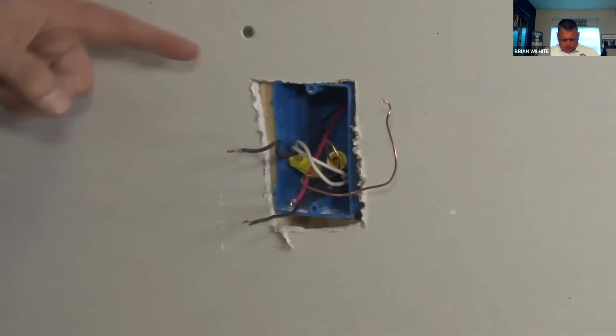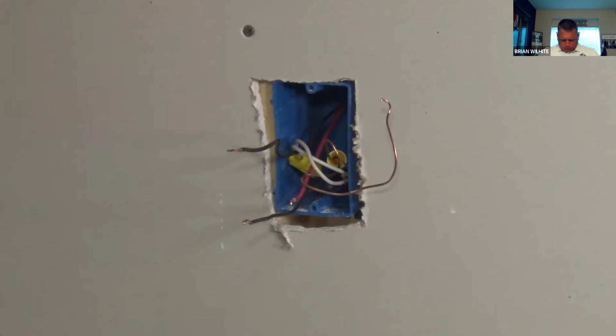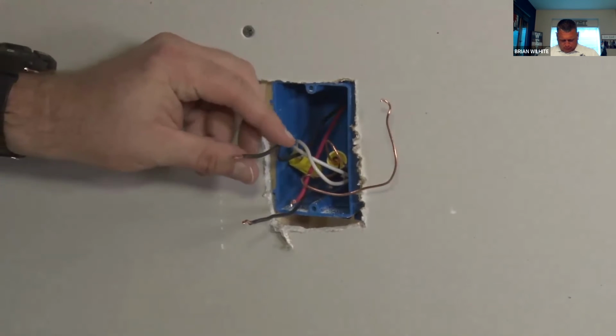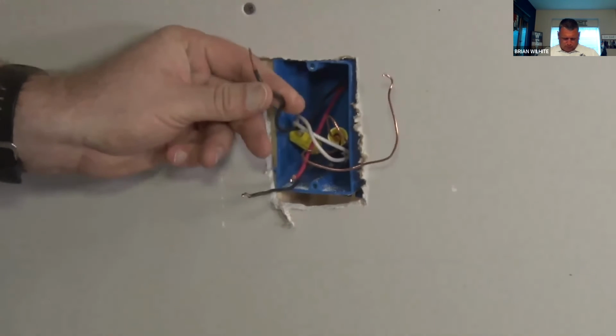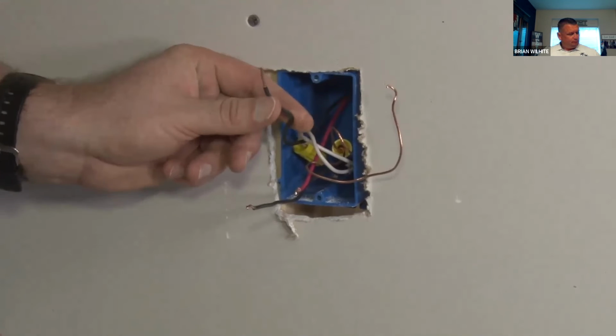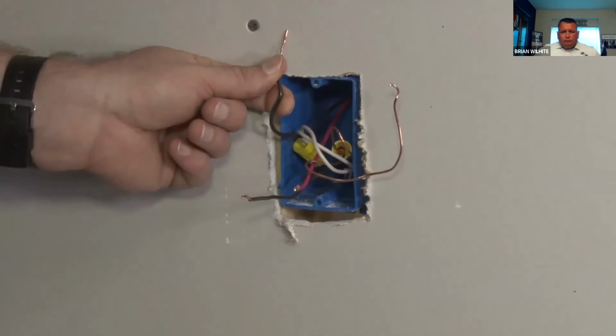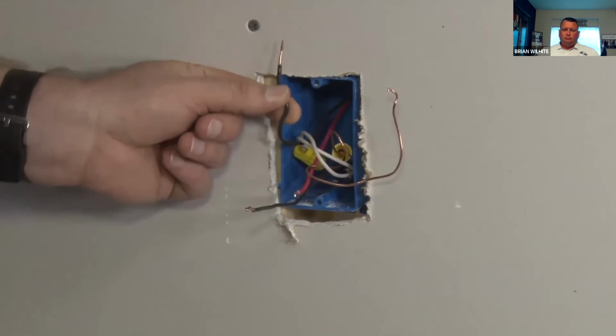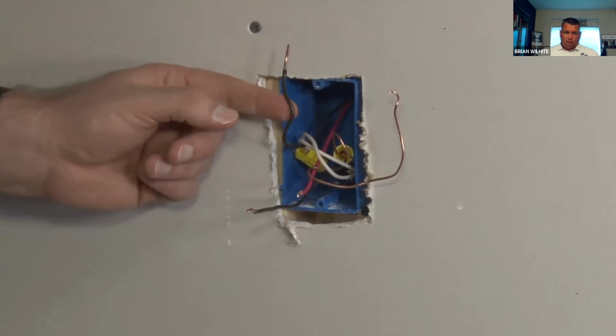Once I've determined that this wire is the live wire, again, I go back to the breaker box, and this time I need to turn the breaker off and use lockout tagout equipment. Since the power is removed and I've determined that this is the hot wire, for right now, I'm just going to bend it up out of the way, keep it identified.